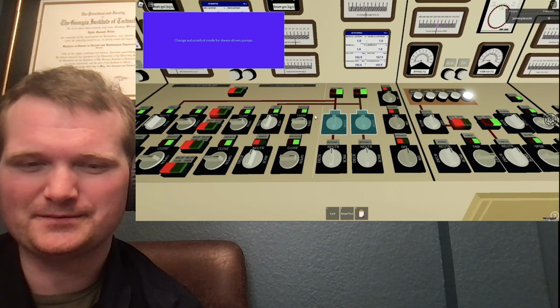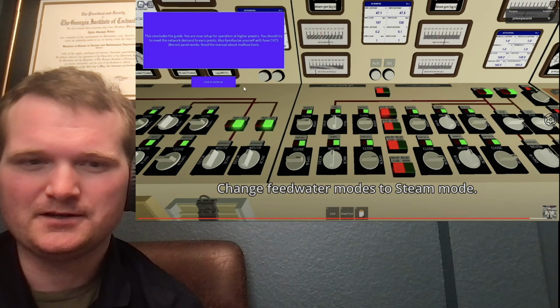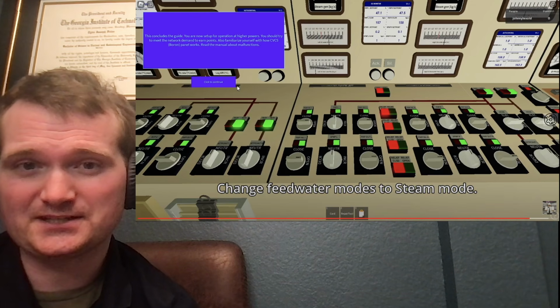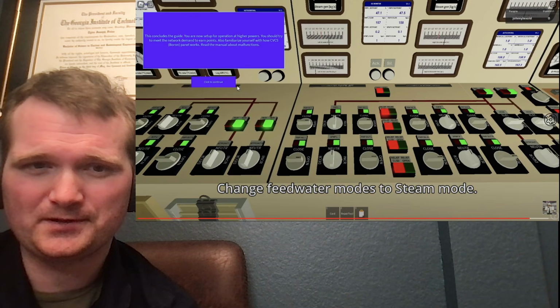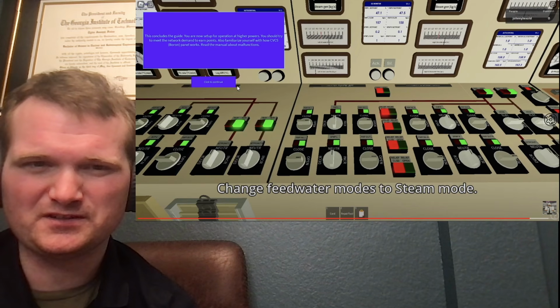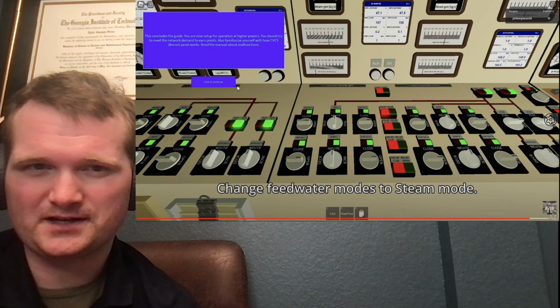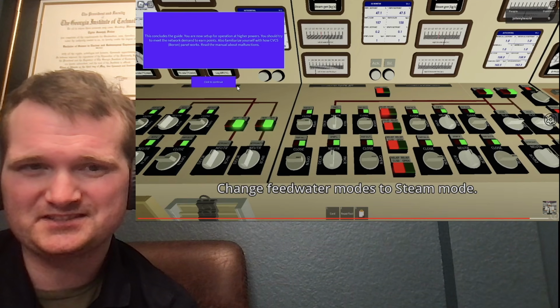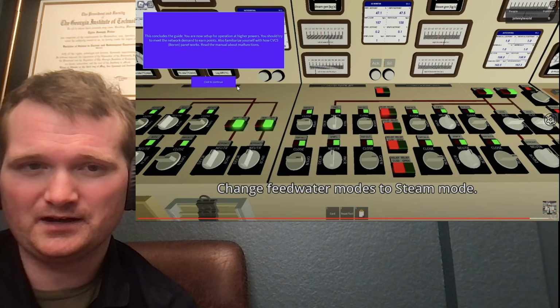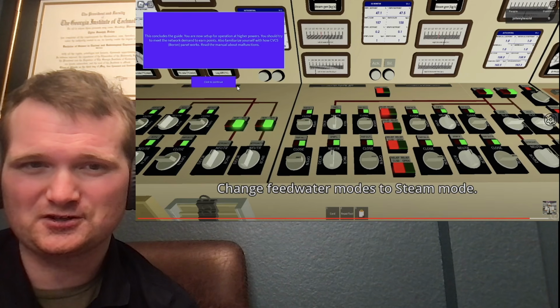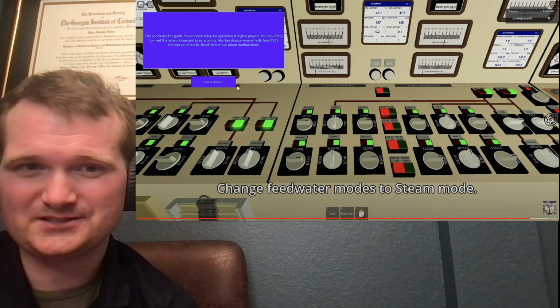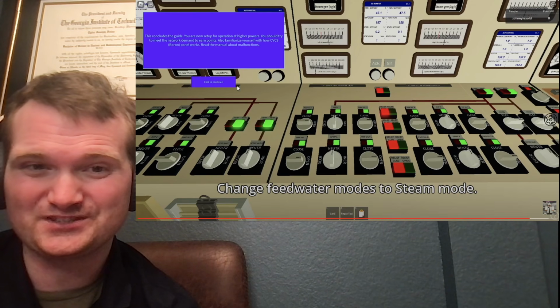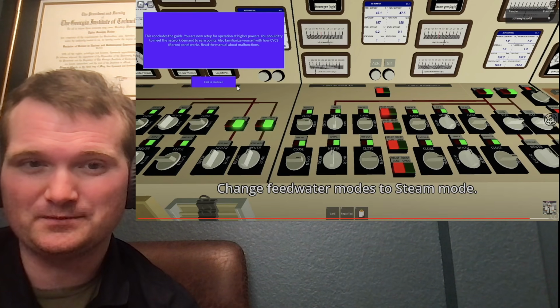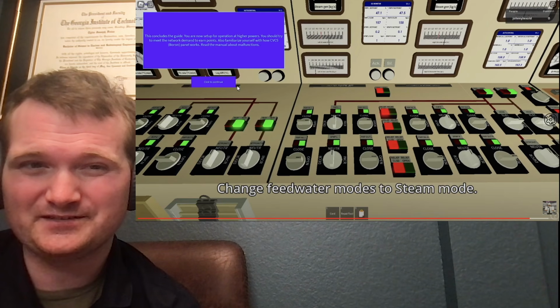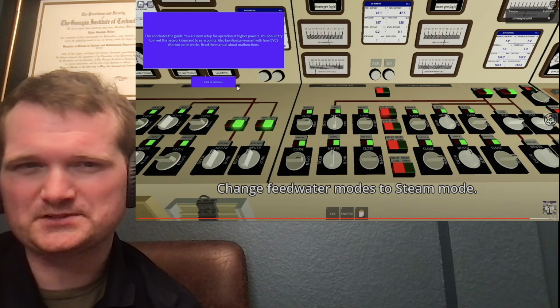Enable second feed water pumps. So you'll see this, you'll turn on additional secondary pumps as you ramp up in power, and you'll do it at various hold points. At the plant we worked at, we had 3 condensate pumps, 3 feed water booster pumps, and 3 steam-driven steam generator feed pumps. We also had a startup feed pump because the turbine-driven feed pumps wouldn't have run because we were just so low in power, but the startup feed pump will get you up to 20%, where you're making more than enough steam to run those other pumps. At full power, they'll all be running, with the exception of the startup feed pump.